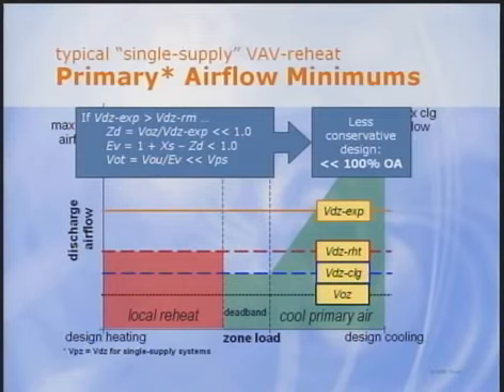Since this expected value is probably greater than the reheat minimum, this approach reduces intake airflow compared with the previous approach. Some designers use Trace 700 to help with this analysis and to help determine minimum settings that lower annual energy use and satisfy Standard 90.1. Other designers use a spreadsheet, like the one that comes with the 62.1 User's Manual, to do a series of what-if calculations in order to find reasonable values for minimum settings and intake airflow. Steve will talk about this approach in a moment.